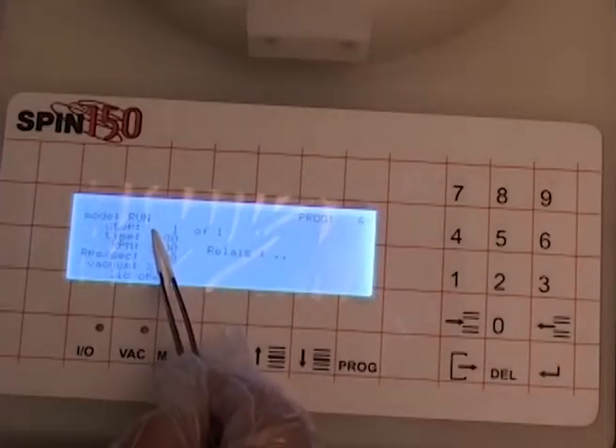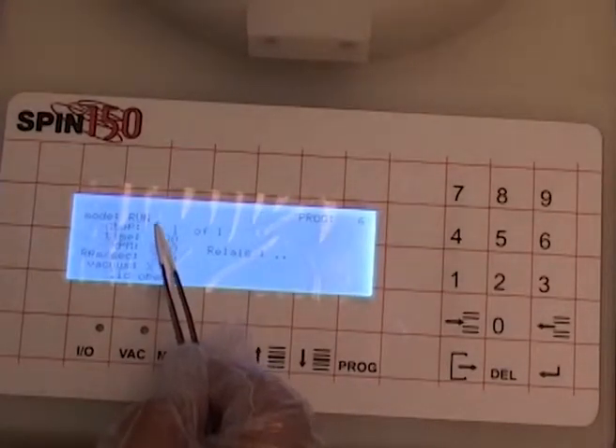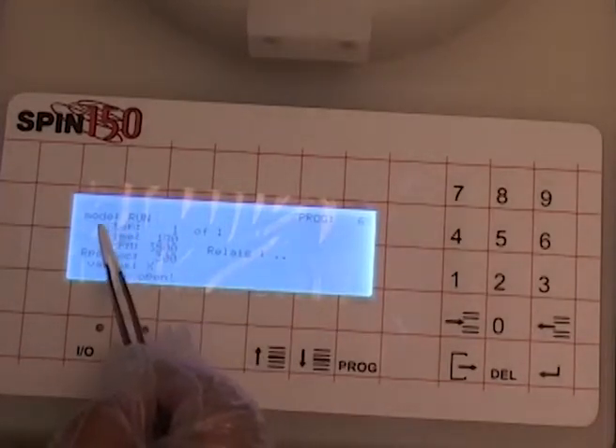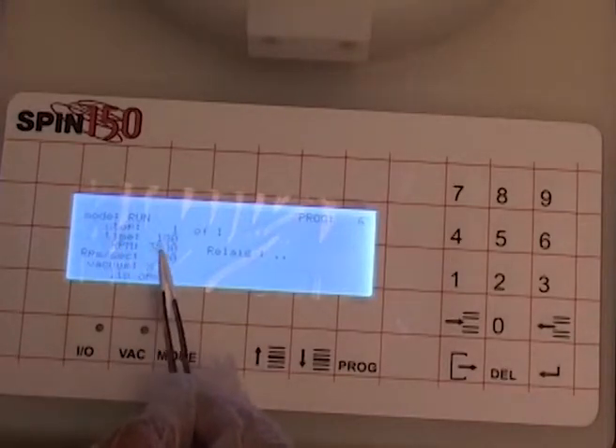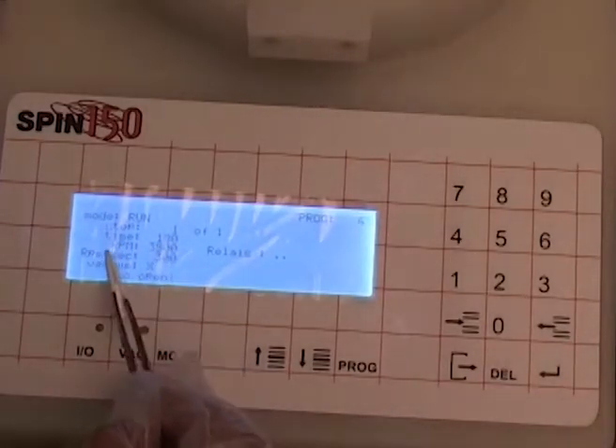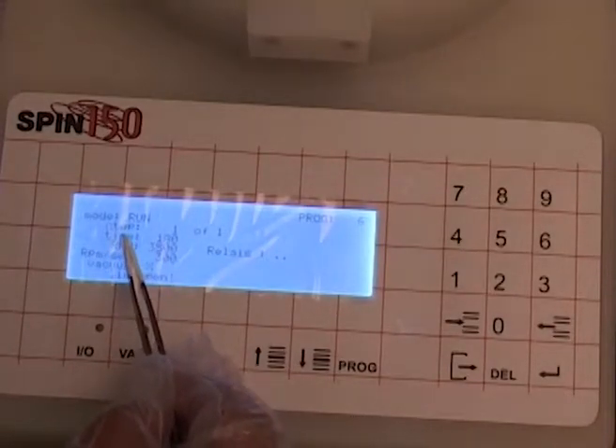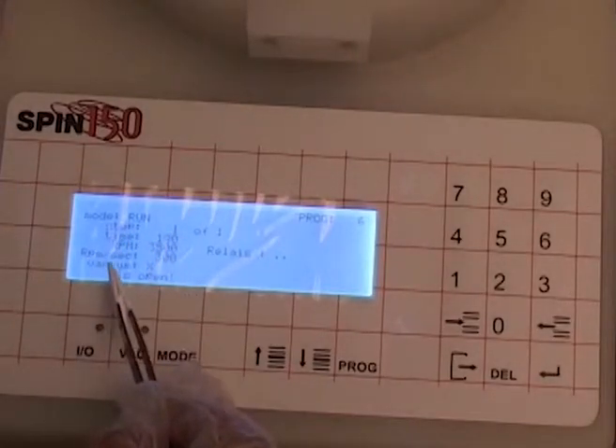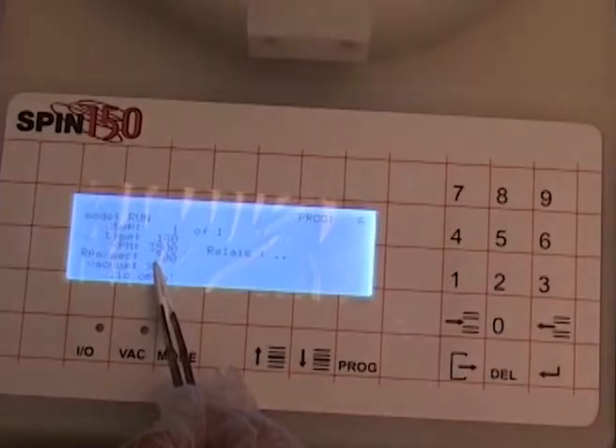Corresponding to this program number, what all steps are there in the program are illustrated just in this particular region. As you are seeing here in the run mode, step 1 of the program illustrates that there would be an RPM of 3500, which is attained at an acceleration of 300 RPM per second. The time of hold for this is about 180 seconds, and this is with an option of vacuum operated, so that the wafer is pulled down while the spinning happens.